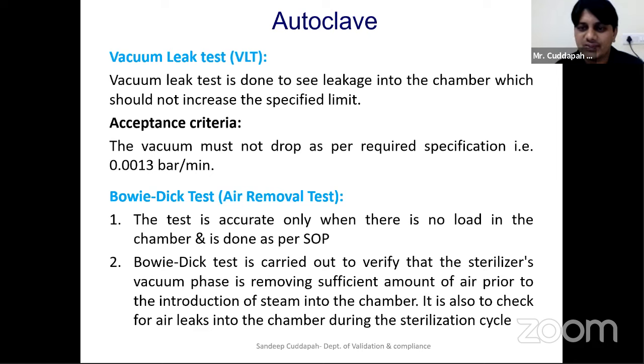So you will do a vacuum leak test. You will make sure whatever pressure you have given inside the equipment is achieved and maintained or not. Through the vacuum leak test, you will verify that there are no leakages in the equipment. Then the Bowie-Dick test is a key test for any autoclave. You will have a standard test kit. You place that standard test kit inside your autoclave and run a small sterilization phase. After sterilization, you see whether your Bowie-Dick kit color has changed or not. It is to prove your equipment is able to create proper vacuum and steam is able to penetrate properly or not. That you verify during this Bowie-Dick test.